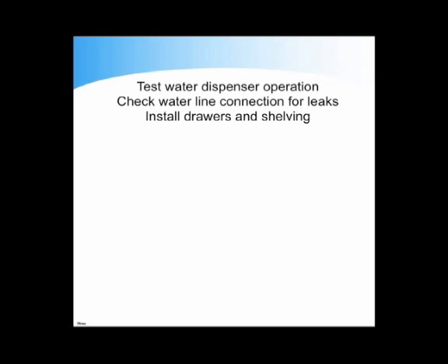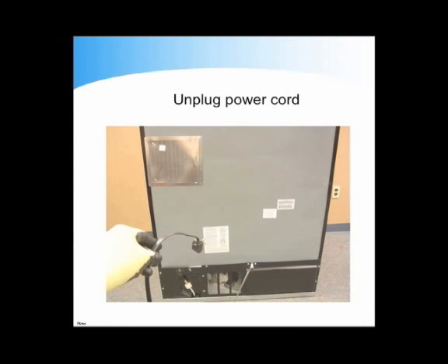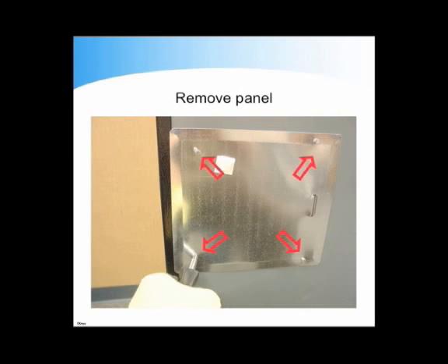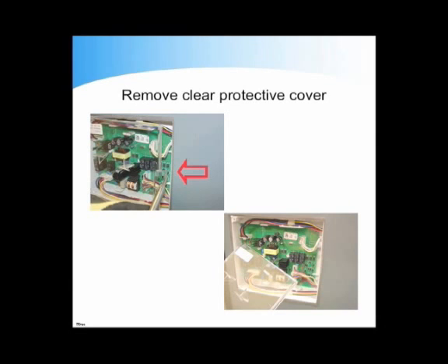Install drawers and shelving. The power supply on the high voltage board may fail, resulting in the dispenser door continually opening and closing. Eventually, the board will fail completely, which results in no cooling. Order a new high voltage board. Unplug the power cord. Remove the panel. Remove the clear protective cover.